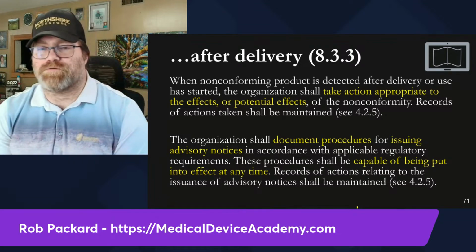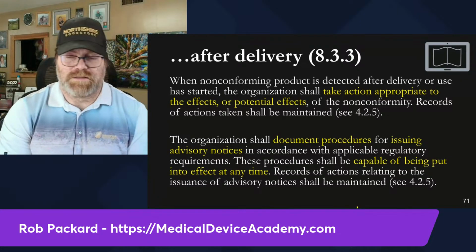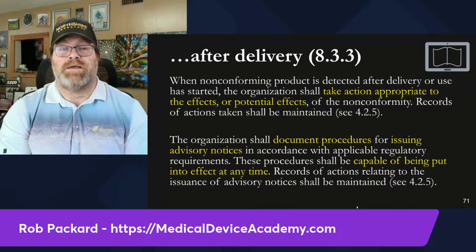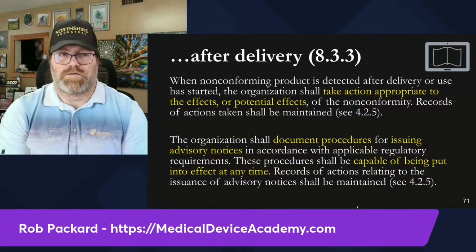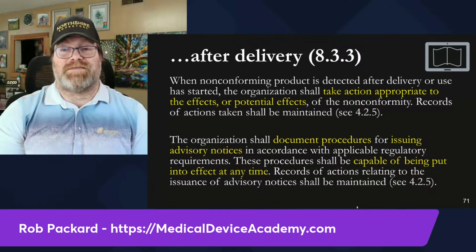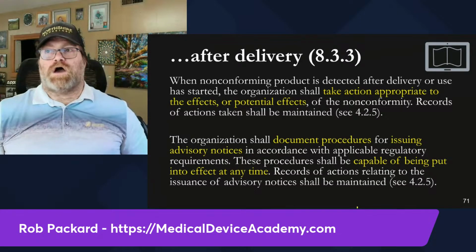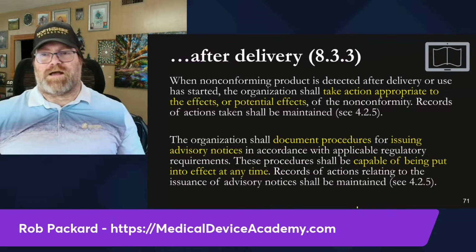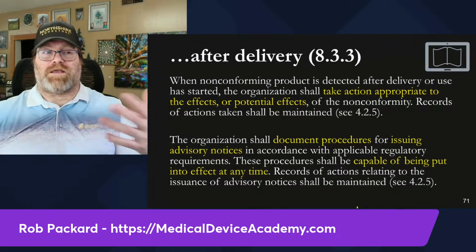You obviously need a procedure for your advisory notices or recalls. You use advisory notices when there's no potential for harm. You use recalls when there's potential for harm, especially serious harm, where you're going to notify: urgent recall, correction, removal. If you're clarifying something in the instructions for use and there's no reason for harm, or you have a new adapter or a new model, so the old model is not out there anymore, maybe it only affects software or firmware, and they won't even see it, but you're making them aware of it.